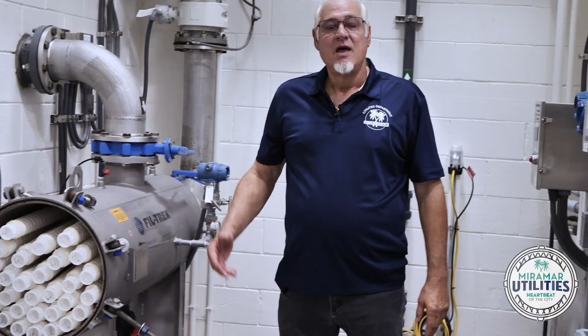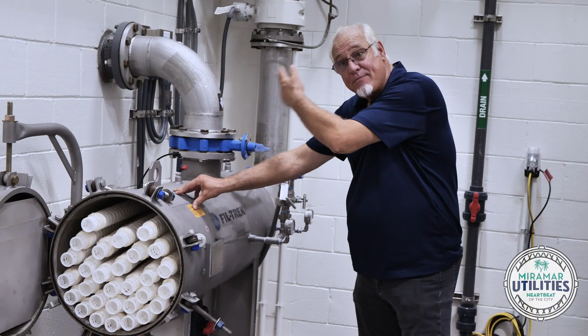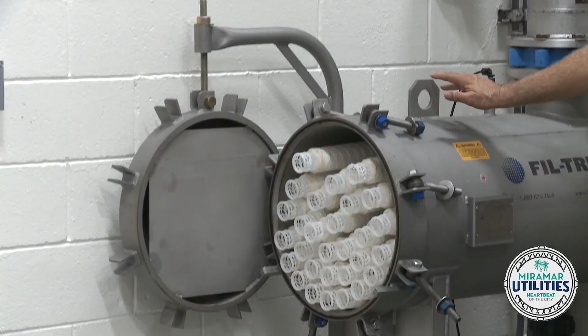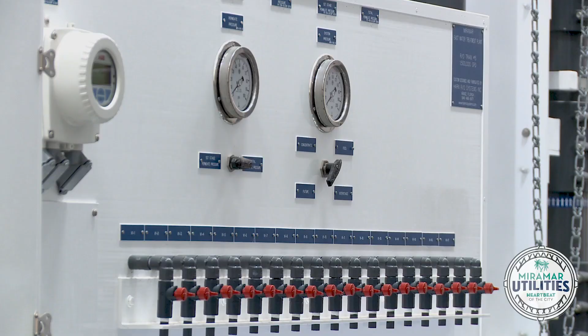This is our bypass system. If we ever want to make more water than the plant's designed for, we can add 5% of the water volume leaving the plant just by taking raw water and bypassing the whole system, and it's only 5%. So it brings up our hardness just a little bit and maybe makes it taste a little better sometimes. Right now we're not using it, but just like the other cartridge filters, we filter the raw water before it goes through. These are 5-micron filters, so only the tiniest little things get past us.